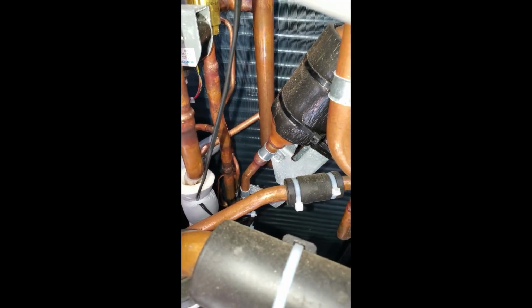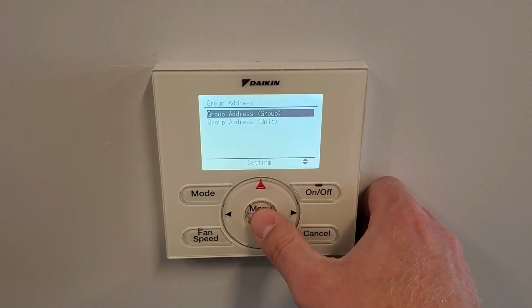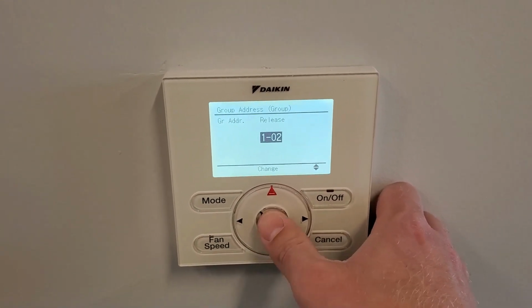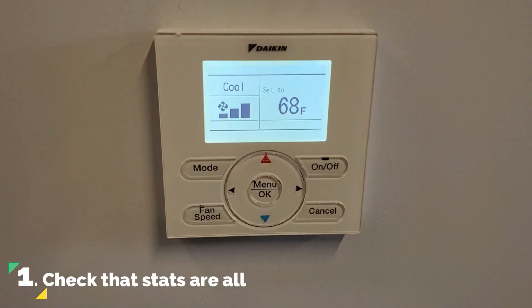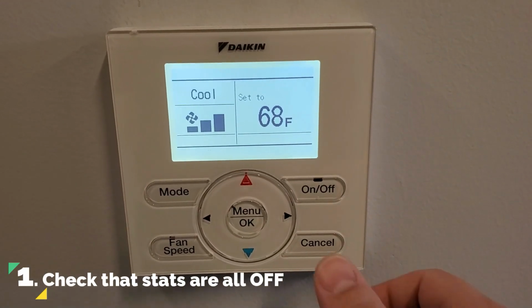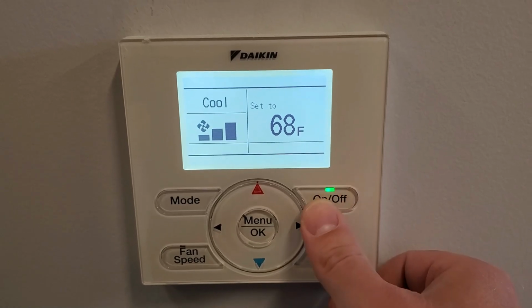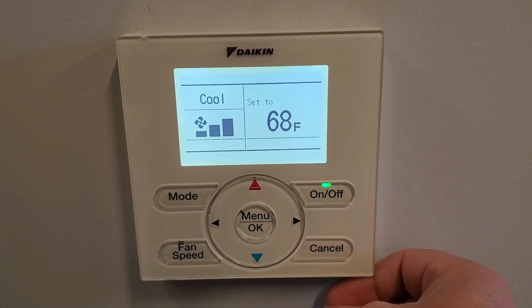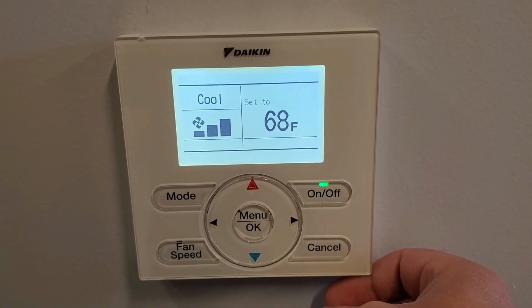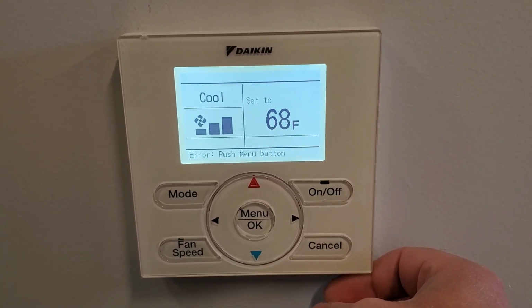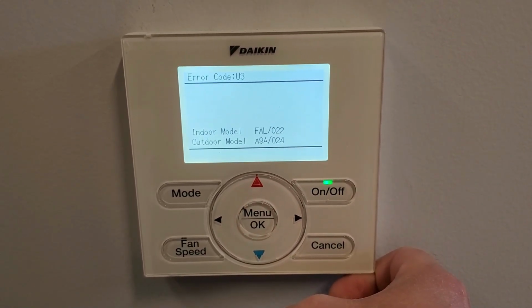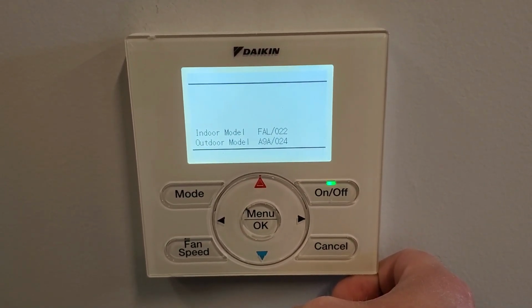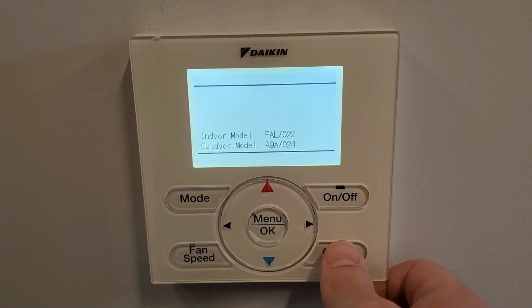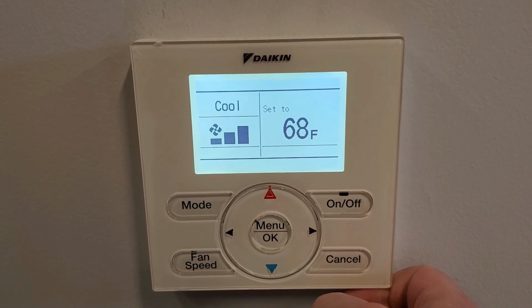Now, in the last video, we left off needing to run the system through something called test operation. We were unable to do this because the outdoor unit had a leak, which is why we completed all of our controls work and programming in that first video. Before you start the test, make sure all the thermostats are in the off position. If any of them are turned on either accidentally or because the end users see the display and think they can operate the system now, you're going to get a U3 error code. If you see this error code, it's because the system has not been ran through the test operation. You'll know there's an error on the nav controller because the on-off button will blink the green LED. Again, make sure you turn off all the thermostats and then proceed to the outdoor unit to start the test operation.